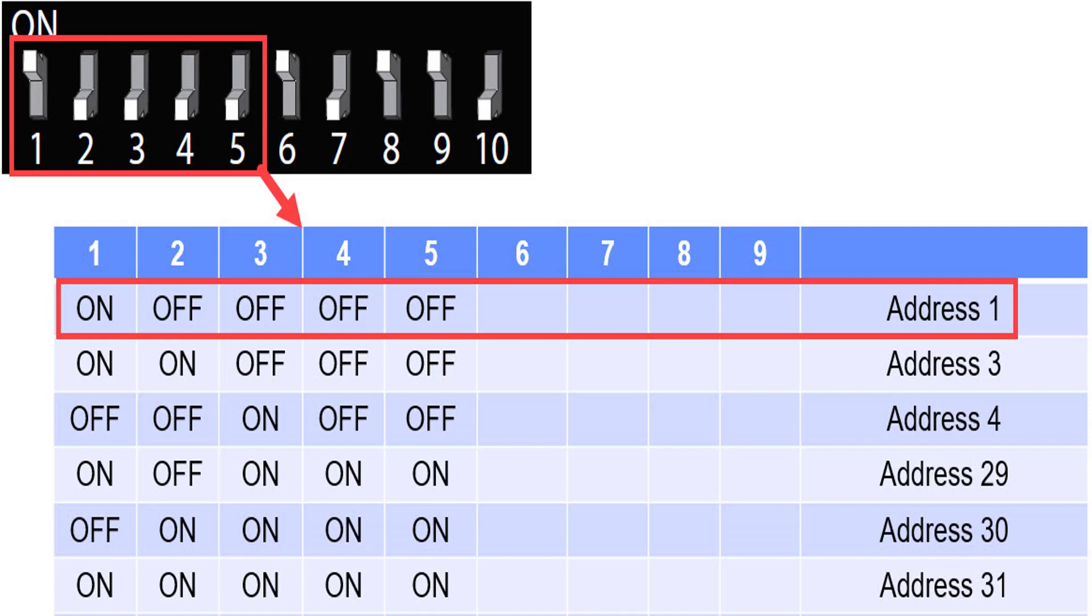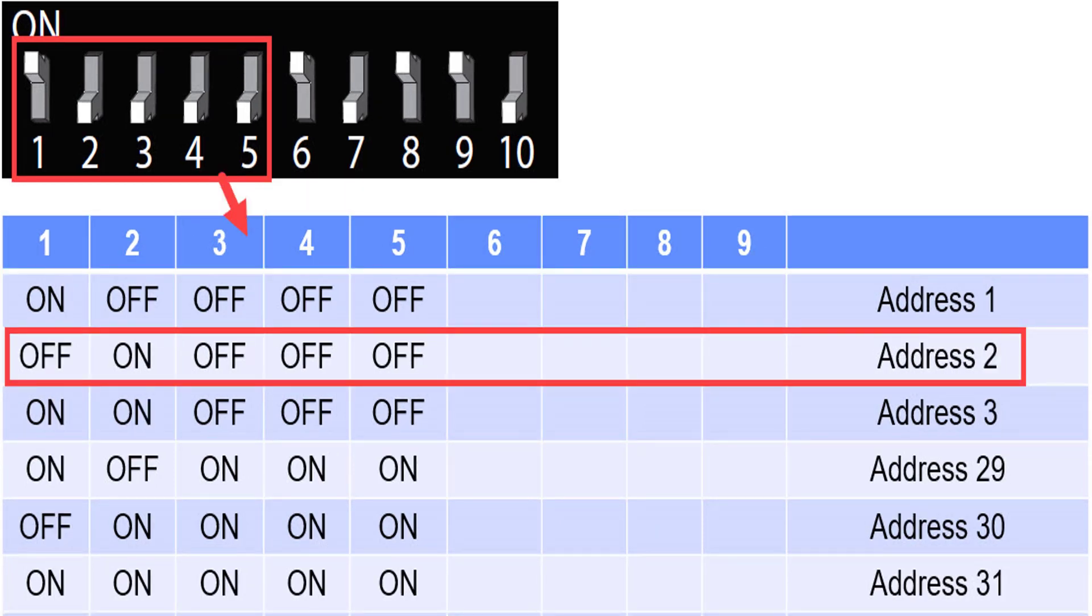If it is the first panel on a loop or a standalone panel, DIP switch 1 must be on. If it's the second panel, DIP switch 2 must be on.